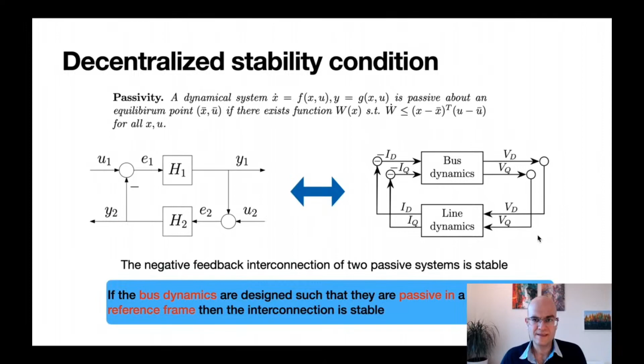However, satisfying this passivity condition is in general a non-trivial problem. For example, this is not satisfied when conventional droop control policies are used in grid-forming inverters. We tried various parameters and were not able to satisfy this passivity property, which implies that more advanced inverter control designs are needed in order to have these stability guarantees by means of decentralized control policies.